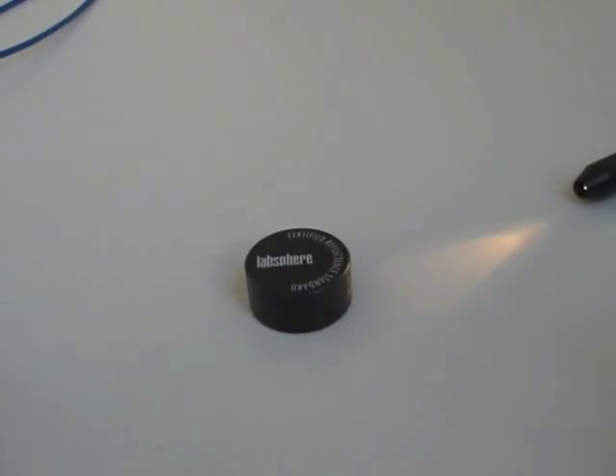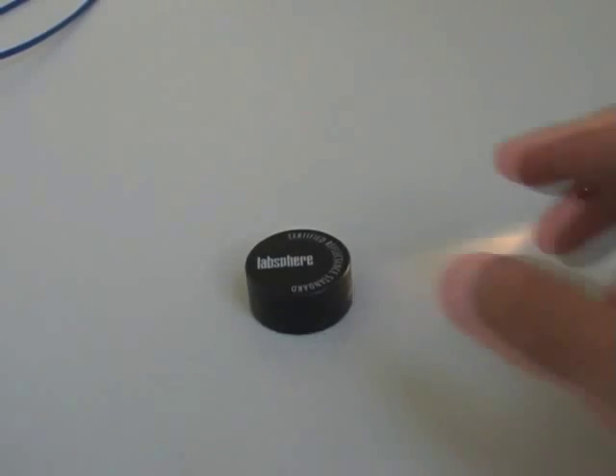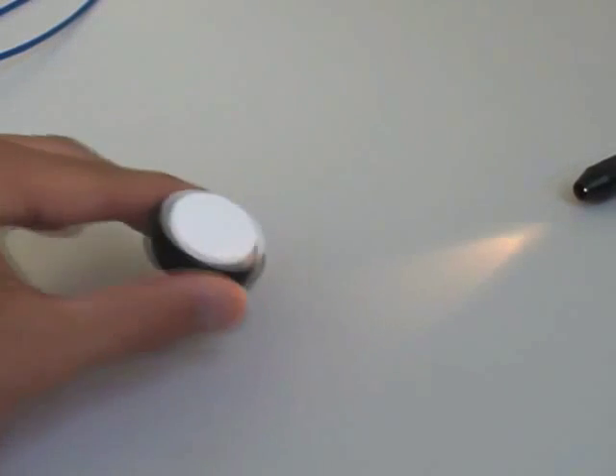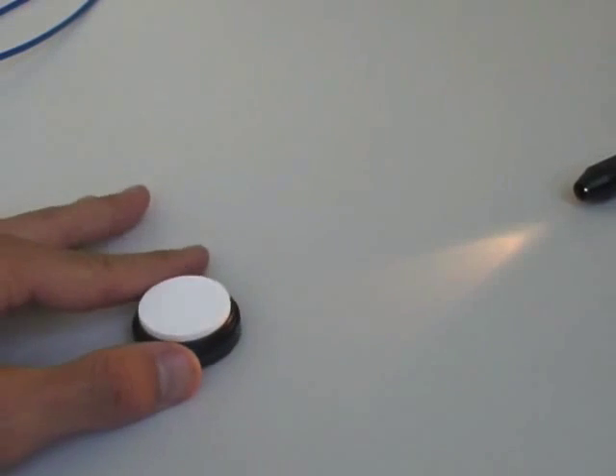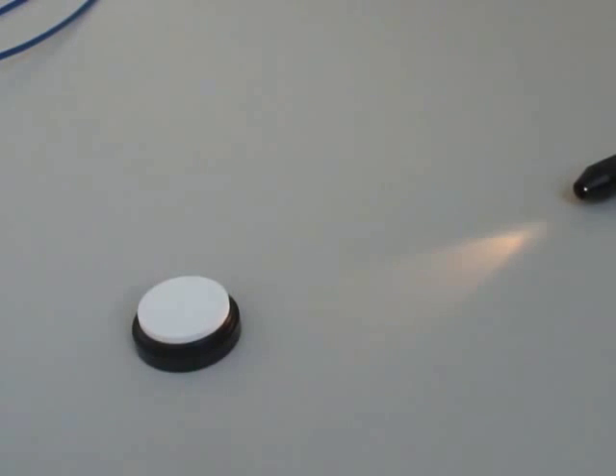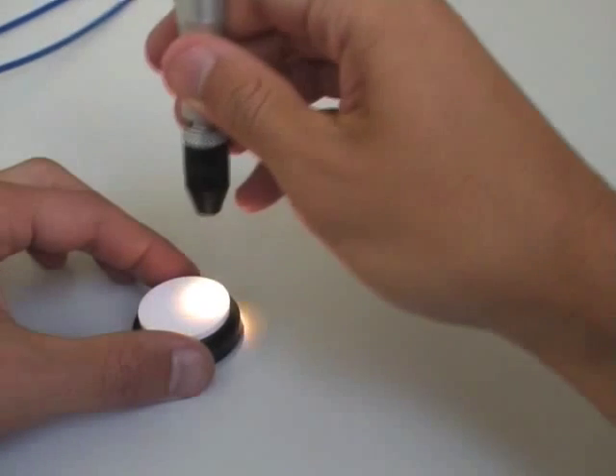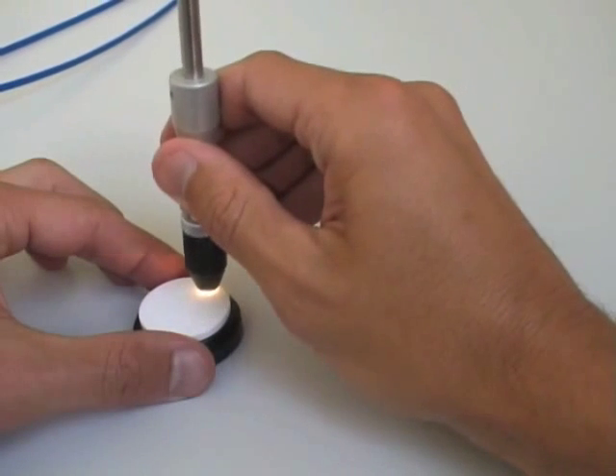To tune the sensitivity of your spectrometer, take the white reference standard. Open it, take the fiber reflection probe, and press it gently onto the reflection standard.